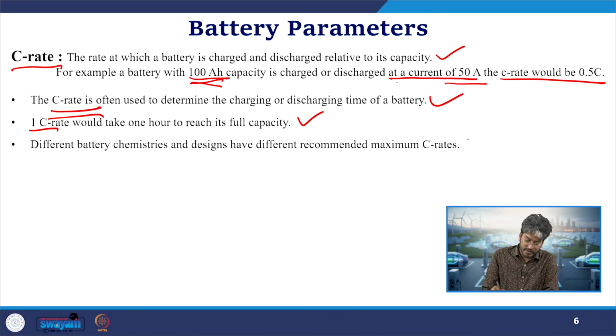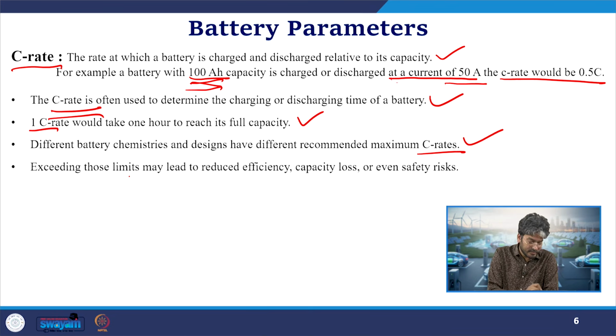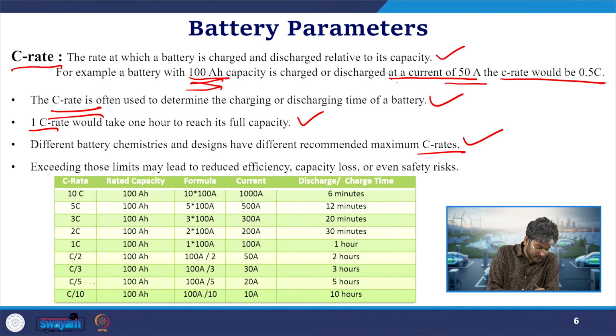Different battery chemistries have different recommendations for maximum C rate. As we discussed, the manufacturer specifies a temperature range. If I increase the C rate, I am handling more and more current. For the same 100 Ah battery bank, if we go for C by 10, it draws a current of 10 amperes and takes 10 hours to charge and discharge.